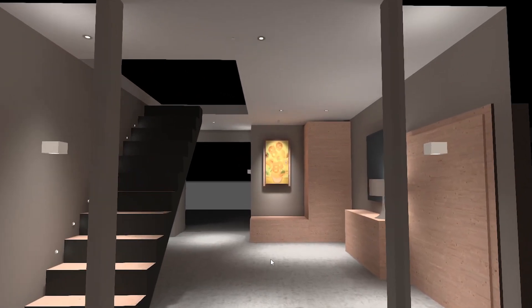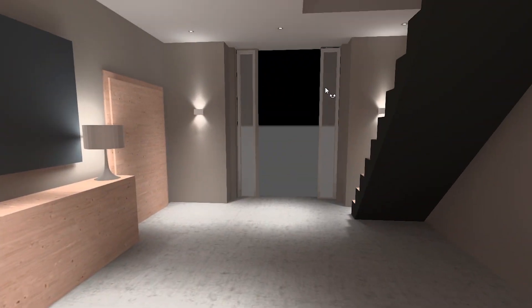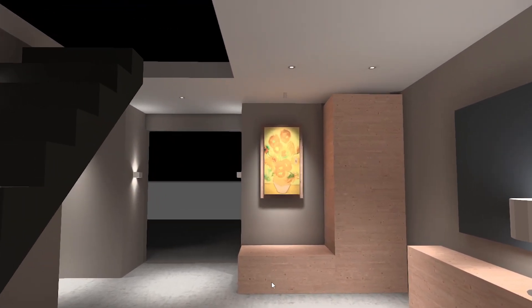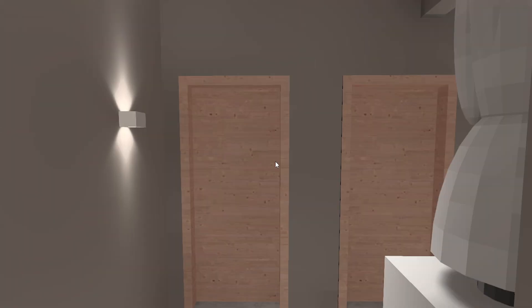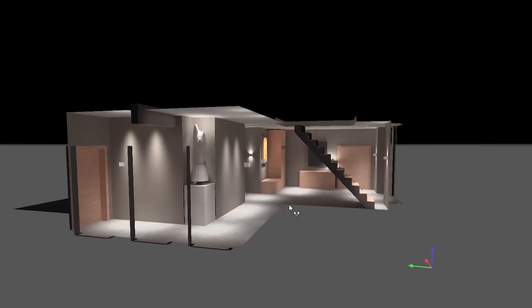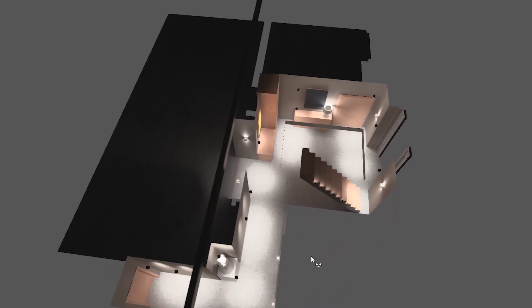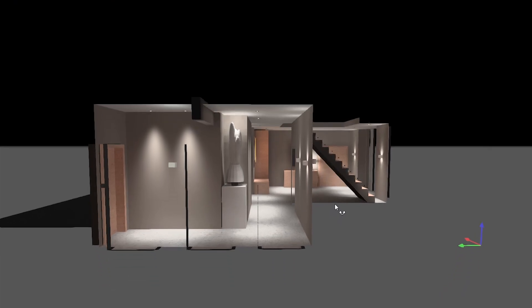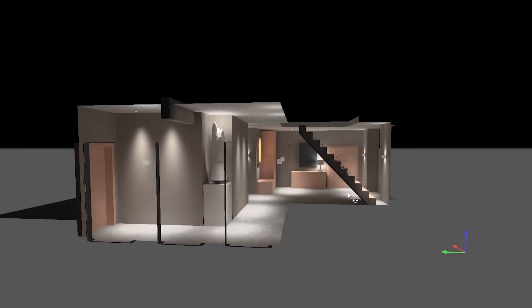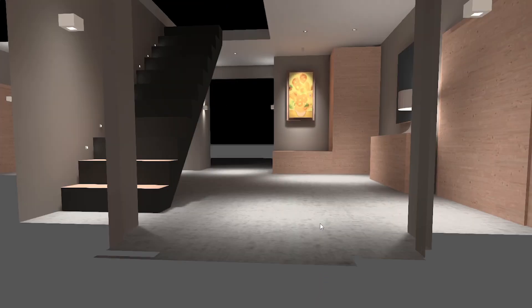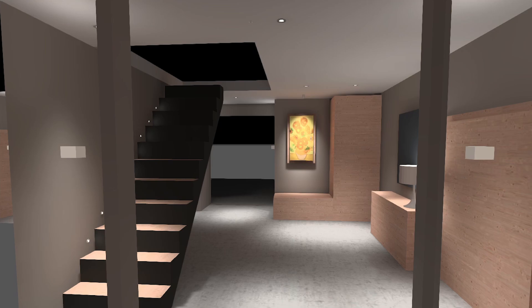In this third example, let's say I have a hallway. On the main entrance end, I am using a Faradite motion sensor. So when I arrive at night time and the lights in the hallway are off, lights will automatically turn on. And on the other end of this hallway, I am controlling the lights from a Lutron keypad by the utility room. Let's program Lutron Homeworks so my hallway turns on automatically ONLY when my lights in the hallway are completely off. However, if I already have lights in my hallway set to any other level by my keypad, nothing will happen — so I won't have an awkward change of illumination in a space that is already lit.